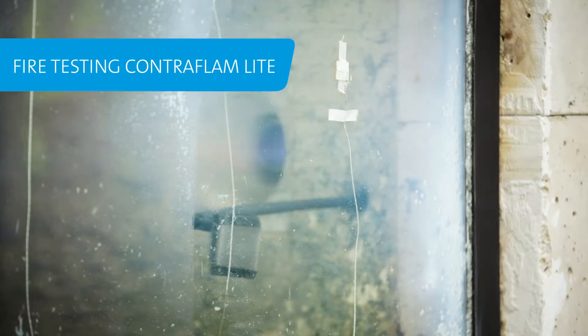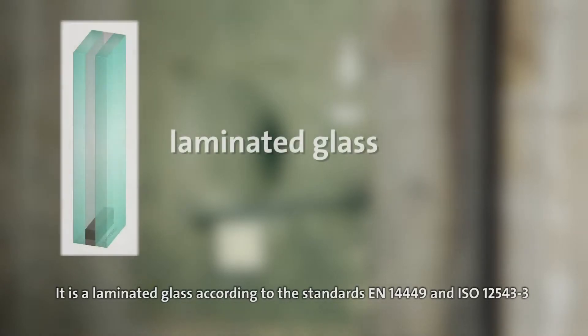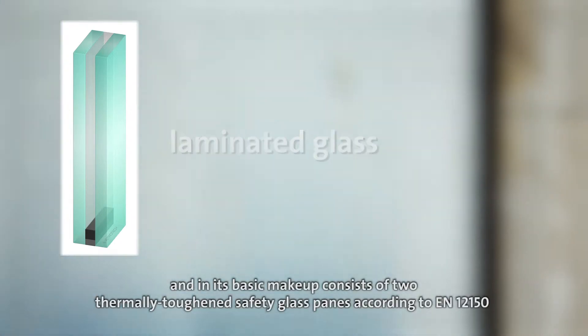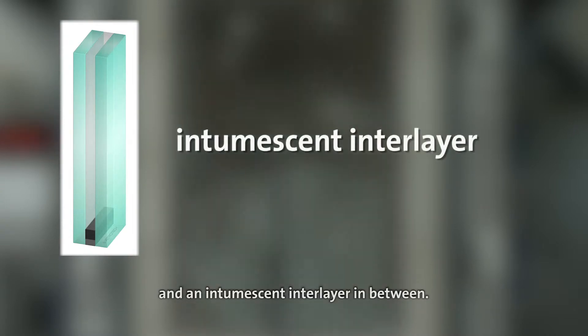Contraflam Lite is Vetrotech's fire resistant glass for the EW classification with safety glass characteristics. It is a laminated glass according to standards EN 14449 and ISO 12543-3, and in its basic makeup consists of two thermally toughened safety glass panes according to EN 12150 and an intumescent interlayer in between.